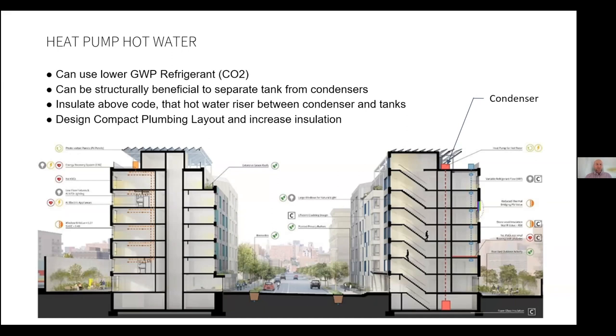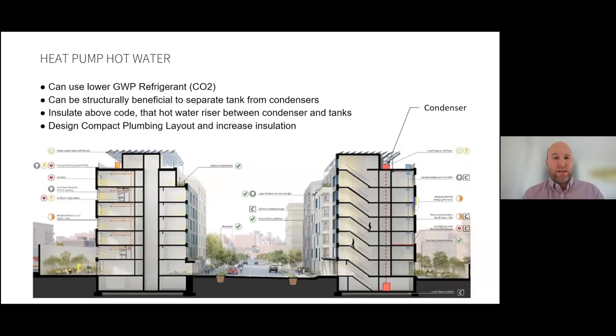First, it can be beneficial to separate the condensers and the storage tanks to alleviate structural loads. On Cooper Park, we have the equipment together on the roof as the building is a cast in place concrete structure and has more flexibility in its design. However, DeKalb Commons, shown here in the diagram, is precast concrete or precast hollow core concrete planks. And moving the tanks to the cellar, reducing the weight on the roof made sense. Also, it's a good idea to insulate the piping between the equipment above code minimums. And lastly, plumbing piping layouts should be made as compact as possible.